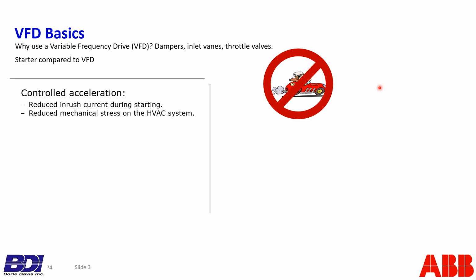And that inrush current will be transferred to a mechanical stress in the system, which, if there are any small fatigue cracks in the impellers or the fan blades, it will begin to propagate those cracks, and eventually you'll lose your fan blades and you'll have maintenance consideration. Well, using the variable frequency drive will reduce that mechanical stress. I like to say in the classes we do in person, you know, when I was 16, my first vehicle was a 61 Studebaker Lark, and it had a V8 289 cubic inch engine with a 3-speed standard shift on the column, clutch, brake, and gas pedal.